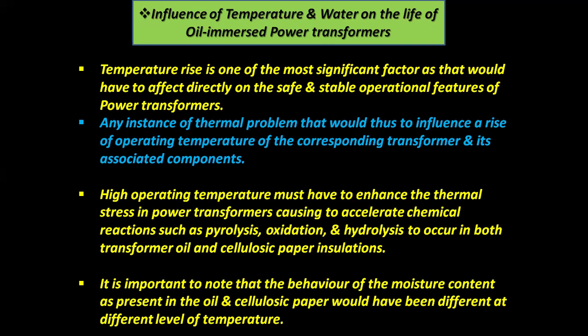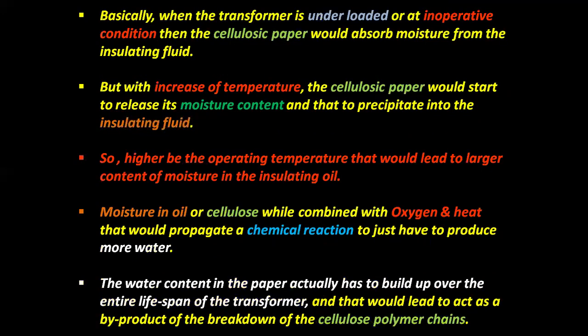It is important to note that the behavior of the moisture content present in the oil and cellulosic paper is different at different levels of temperature. Basically, when the transformer is underloaded or in an inoperative condition, the cellulosic paper absorbs moisture from the insulating fluid, that is, from the oil. But with increase of temperature, the cellulosic paper starts to release its moisture content, which precipitates into the insulating fluid. So, the higher the operating temperature, the larger the content of moisture in the insulating oil.